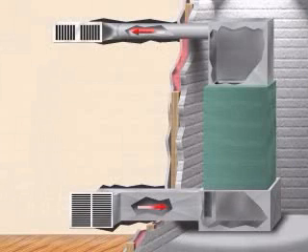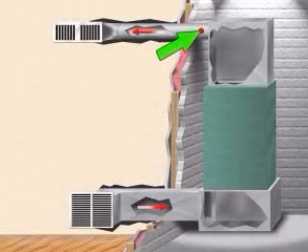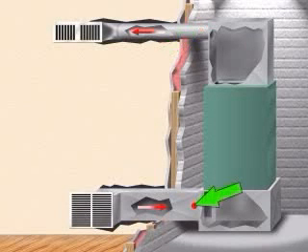To determine if the air flow is correct, make a temperature rise check. Insert a thermometer in the supply air duct as close to the furnace as possible, yet out of line of sight of the heat exchanger. Insert a thermometer in the return air duct as close to the furnace as possible.